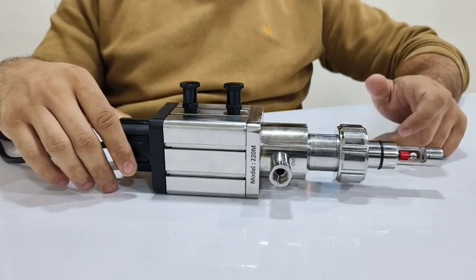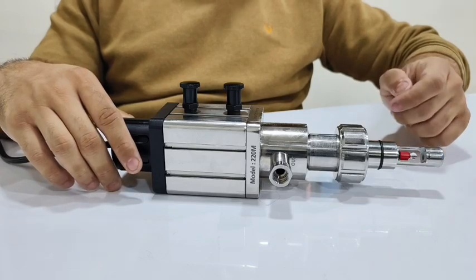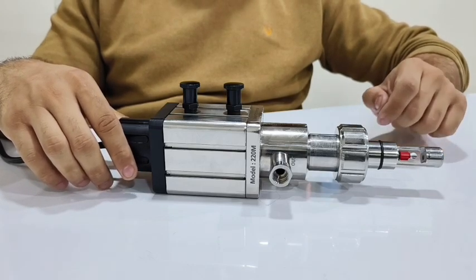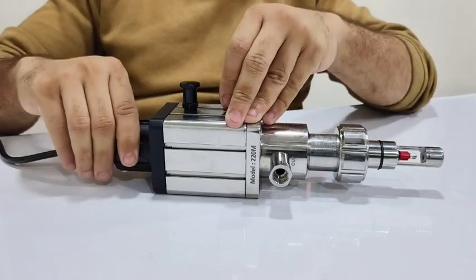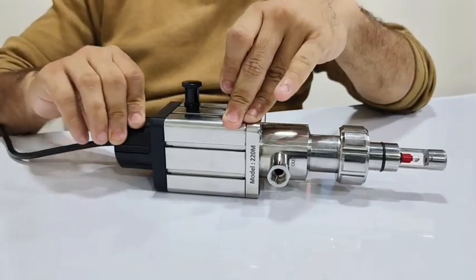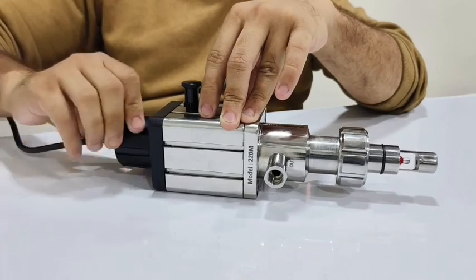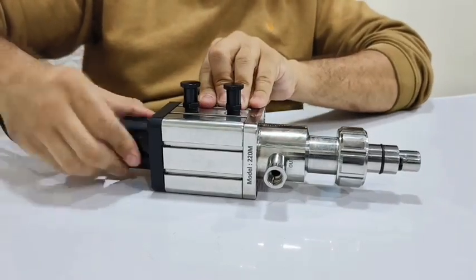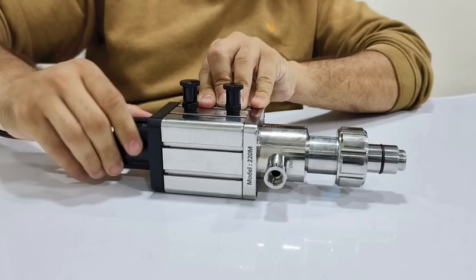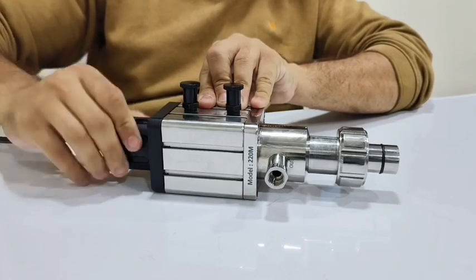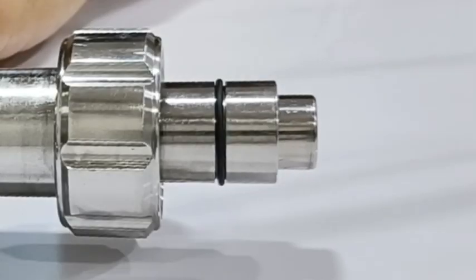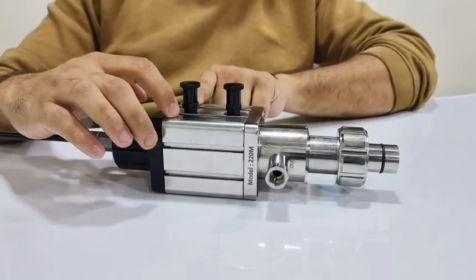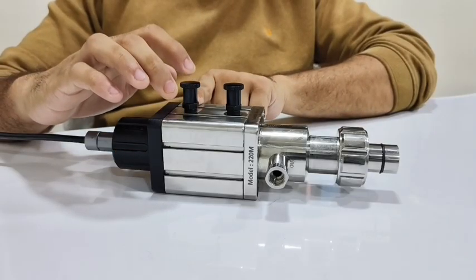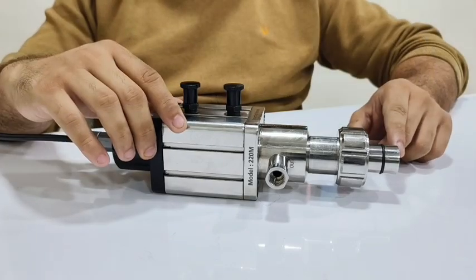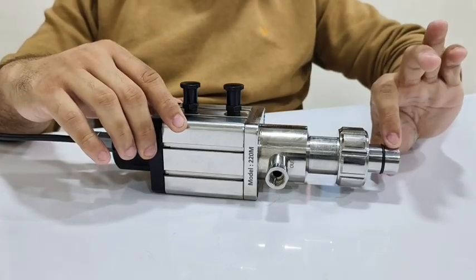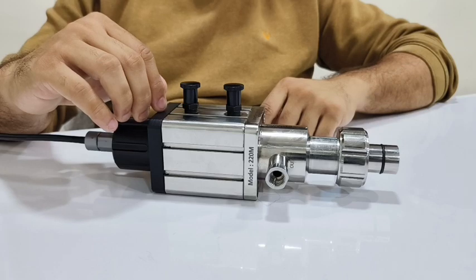come live. In the situation of calibration requirement of the pH electrode during the batch, you can unlatch this service position latch and retract the sensor completely out of the process by rotating the rotary nut. It will come back to the service position and get locked in the service position. In the service position, as you can see, the system is completely retracted inside of the retractable housing chamber.